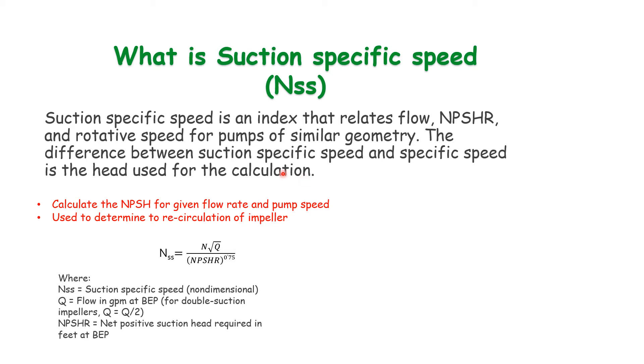If we know the suction specific speed, then we can calculate the NPSHR for a given flow rate and pump speed. Similarly, suction specific speed is normally used to determine the recirculation of the impeller. As we discussed, it's a combination of three parameters.